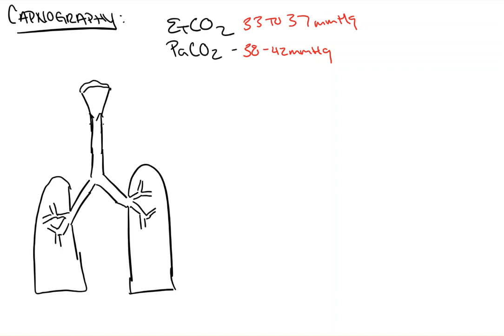So first, before we even look at the tracing, we need to get a general idea of how the technology works, and if you watch the video on the pulse oximeter, the concept is the exact same. There is a light emission source on one side, we call this emission, and on the other side, there is a light detection source.